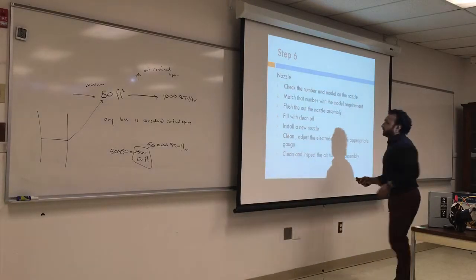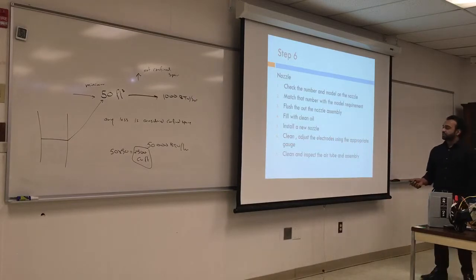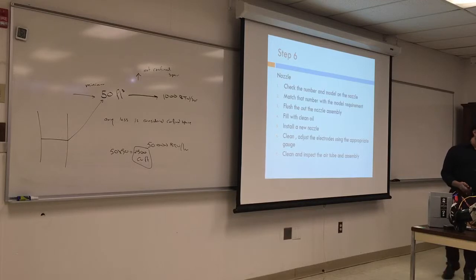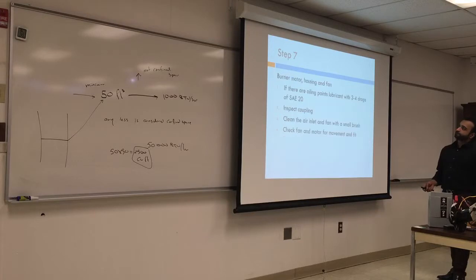Install a new nozzle, clean, and adjust the electrodes using the appropriate gauge for that model. If there is no gauge and the model is very old, what is the distance? It's 1/8 of an inch. And clean and inspect the air tube and assembly.